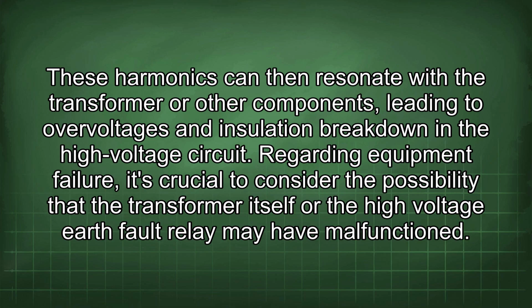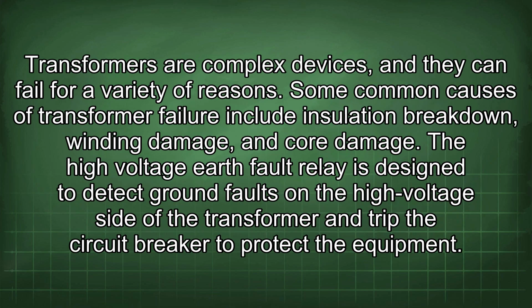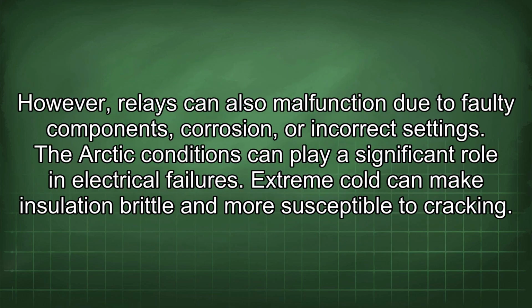Regarding equipment failure, it's crucial to consider the possibility that the transformer itself or the high-voltage earth-fault relay may have malfunctioned. Transformers are complex devices, and they can fail for a variety of reasons. Some common causes of transformer failure include insulation breakdown, winding damage, and core damage. The high-voltage earth-fault relay is designed to detect ground faults on the high-voltage side of the transformer and trip the circuit breaker to protect the equipment. However, relays can also malfunction due to faulty components, corrosion, or incorrect settings.